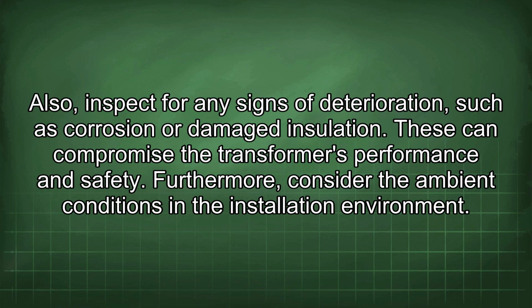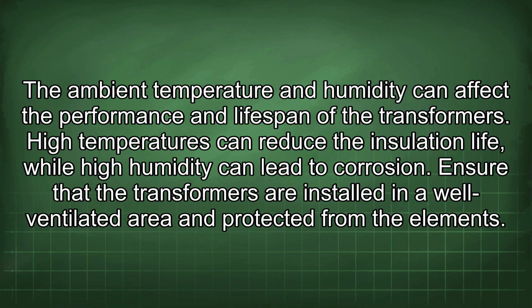Furthermore, consider the ambient conditions and the installation environment. The ambient temperature and humidity can affect the performance and lifespan of the transformers. High temperatures can reduce the insulation life, while high humidity can lead to corrosion. Ensure that the transformers are installed in a well-ventilated area and protected from the elements.